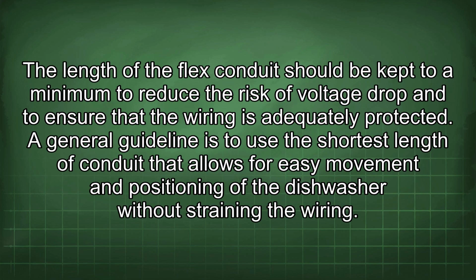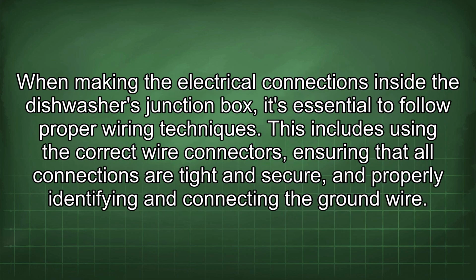The length of the flex conduit should be kept to a minimum to reduce the risk of voltage drop and to ensure that the wiring is adequately protected. The general guideline is to use the shortest length of conduit that allows for easy movement and positioning of the dishwasher without straining the wiring. When making the electrical connections inside the dishwasher's junction box, it's essential to follow proper wiring techniques. This includes using the correct wire connectors, ensuring that all connections are tight and secure, and properly identifying and connecting the ground wire.